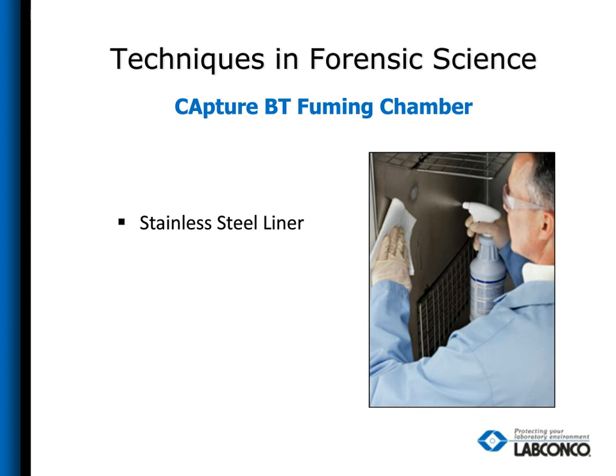The Capture BT stainless steel interior liner makes cleaning very easy. During fuming cycles, CA deposits will build up on the interior walls of the fuming chamber. Because the CA has a high affinity to itself, many new fumes generated will be more attracted to the CA deposits on the walls than the evidence within the chamber, so it is important to clean the fuming chamber frequently. CA deposits are removed very easily from the stainless steel walls with stainless steel cleaner. End users simply need to spray and wipe deposits.